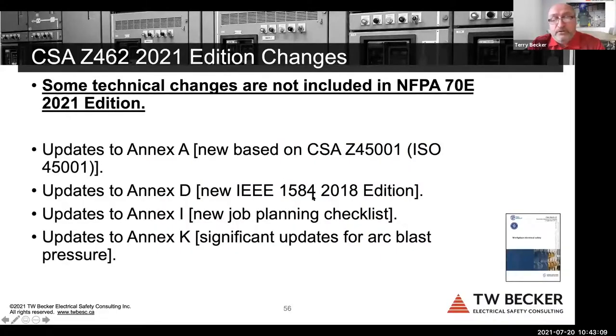Now, the annexes in Z462, this is again where we clean things up. And what happened too is CSA adopted ISO 45001. So we rewrote Annex A, and it's an amazing annex correlating how Z462 can be applied against an occupational health and safety management system, and ultimately to build an electrical safety program. Again, all the old formulas have been deleted from both 70E and Z462, and there's just some introductory text to reference the new 2018 edition. Appropriately get rid of the formulas. Go check out the formulas in the actual IEEE 1584.